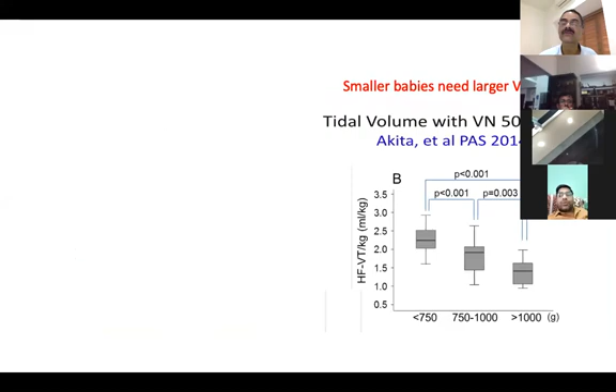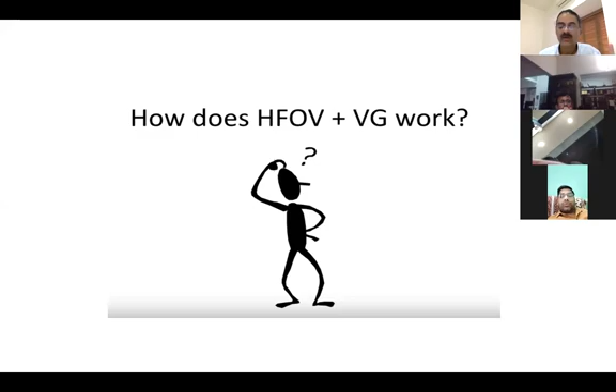HFOV-VG is actually the brand name of the ventilator that I am using, VN500, that says HFO plus VG, the Drager terminology, volume guarantee. SLE 6000 uses a different term. So basically it is all targeting tidal volume. The concepts are similar actually. You set a target tidal volume like in conventional ventilation. Then, where in conventional ventilation you set a PIP max, here you set an amplitude max. And the microprocessor will adjust the amplitude to maintain that tidal volume.